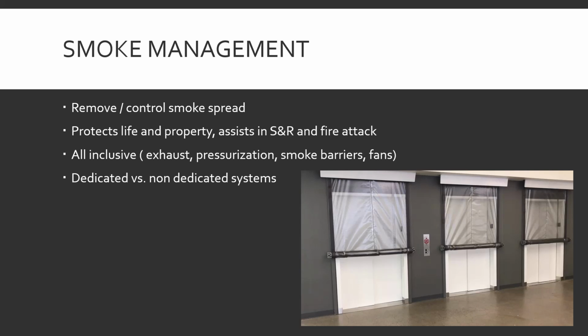Smoke barriers, that's like these guys over the elevator doors. They're used to seal off, maybe not stairwells because those are evacuation routes, but like elevators, where if smoke gets in here, it has free reign over all the floors of the building because that's the elevator shaft. There's no barriers in there. But the smoke barrier keeps the smoke out of the elevator system, therefore it keeps it from running rampant throughout the building. And then fans, again. Fans are just trying to dissipate smoke, guide smoke, that kind of thing.